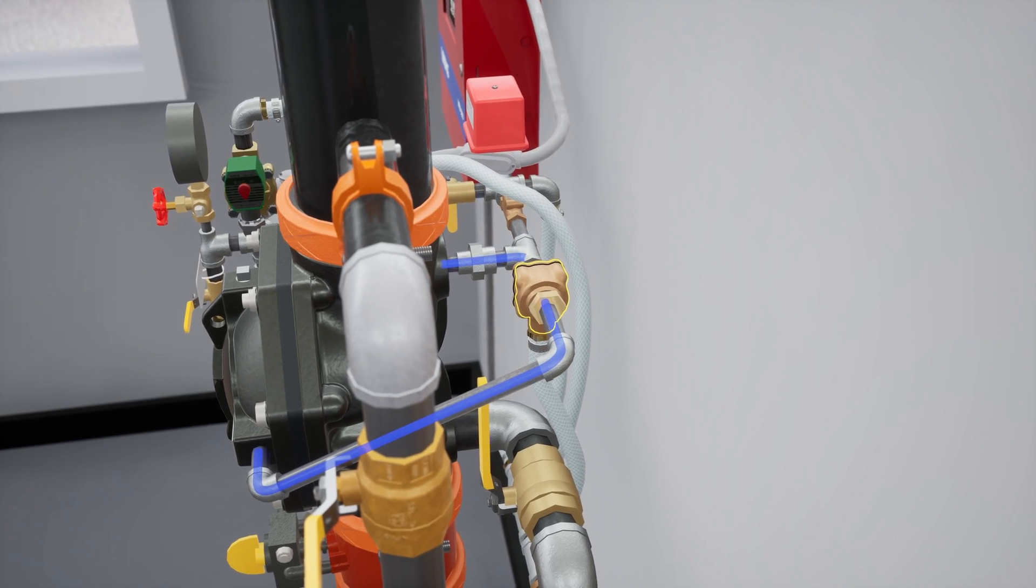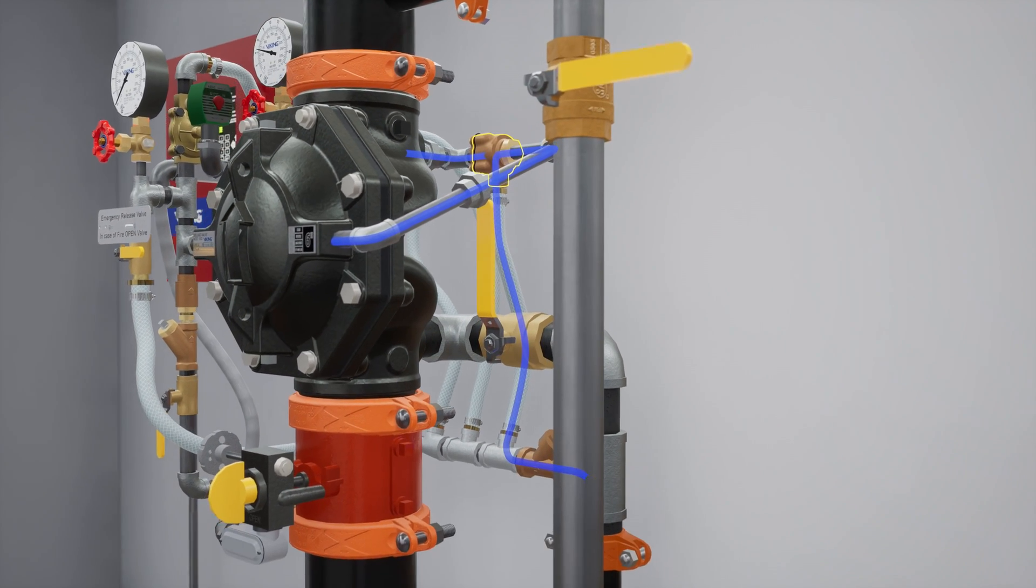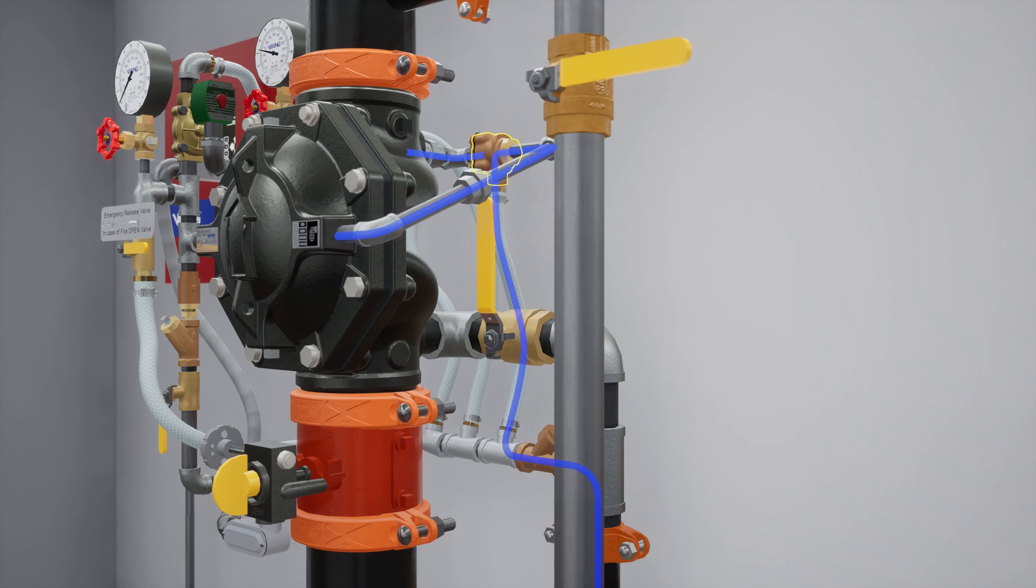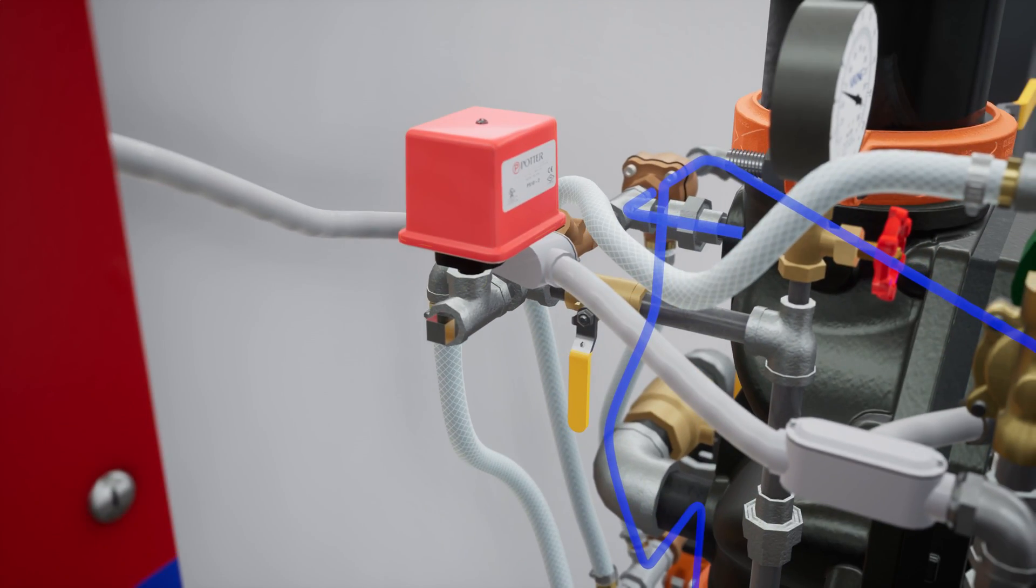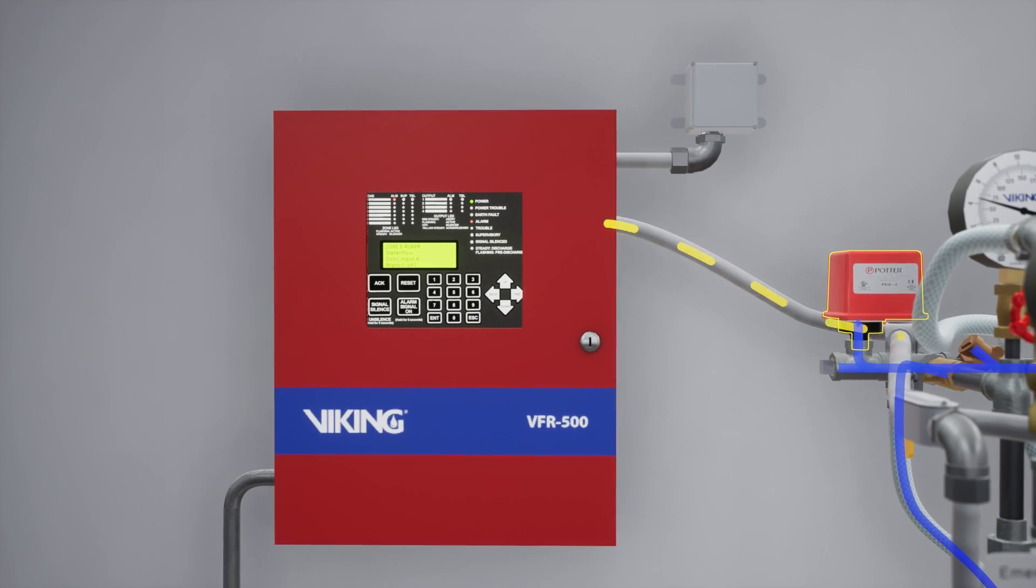The PORV is activated when water from the main supply forces the pushrod open, redirecting prime water out into the drain. Simultaneously, water will also fill the trim leading to the water flow alarm, causing it to activate, alerting the VFR-500 release control panel.